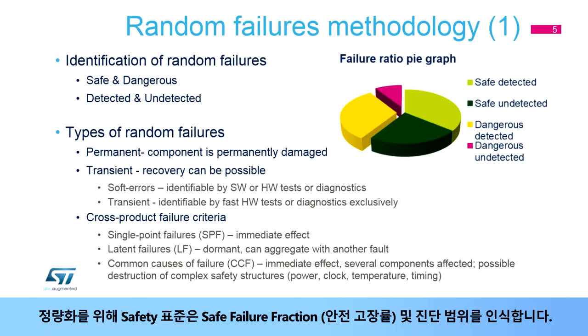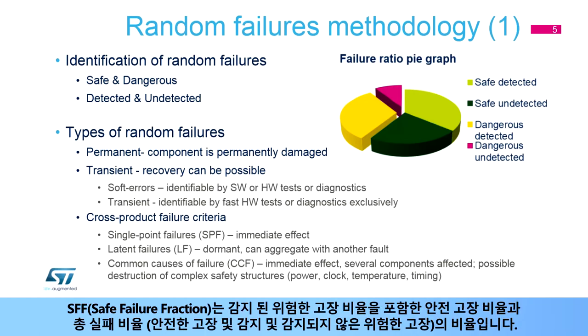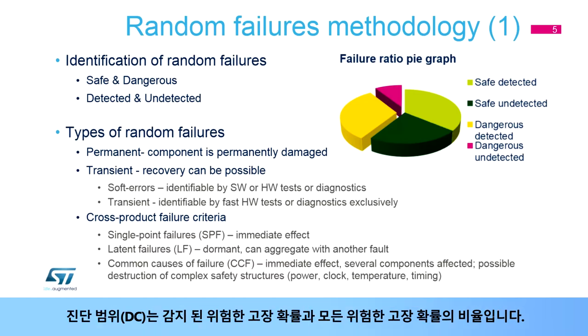For quantification purposes, safety standards recognize a safe failure fraction and diagnostic coverage. The safe failure fraction, or SFF, is the ratio of the rate of safe failures, including the rate of detected dangerous failures, to the total failure rate of safe failures as well as detected and undetected dangerous failures. The diagnostic coverage, or DC, is the ratio of the probability of detected dangerous failures to the probability of all dangerous failures.